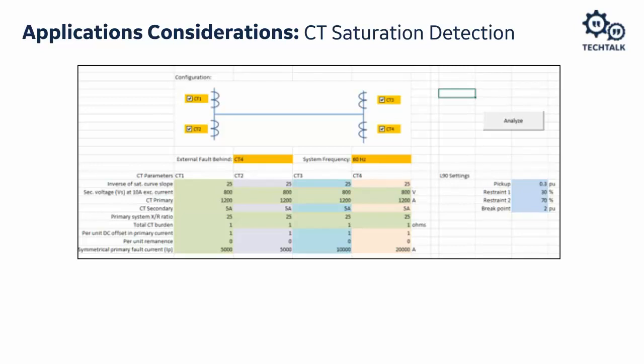Today there are many investments in protective relays to deal with saturation properly, but we still want to be sure the application is safe. An application tool available on our website helps estimate CT saturation impact — you enter the CT characteristic, fault levels, CT ratios, and it gives you the relay response. This helps model the exact CT and estimate the relay's response to various scenarios.